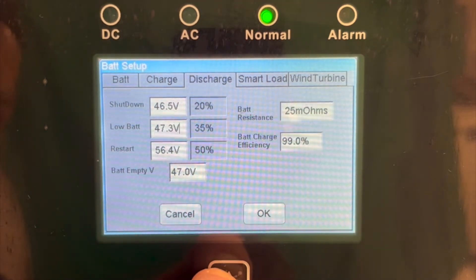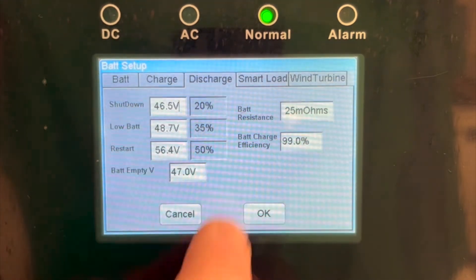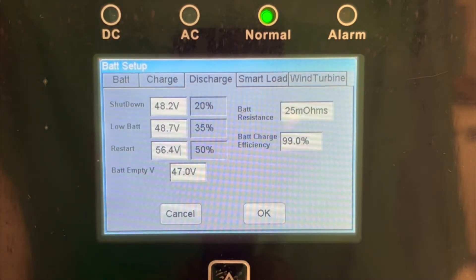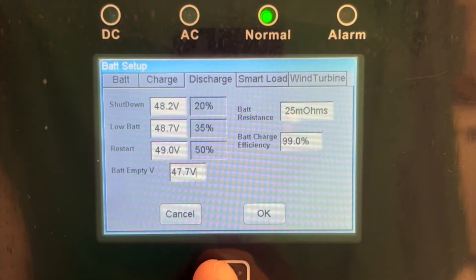On the Discharge tab, Inverter Shutdown voltage should be set to 48.2 volts. However, you'll see that you first need to increase the low battery alarm voltage to about 0.5 volts higher than the target shutdown voltage before setting the appropriate shutdown voltage. Restart voltage should be set to 49 volts and battery empty volts to 47.7 volts.